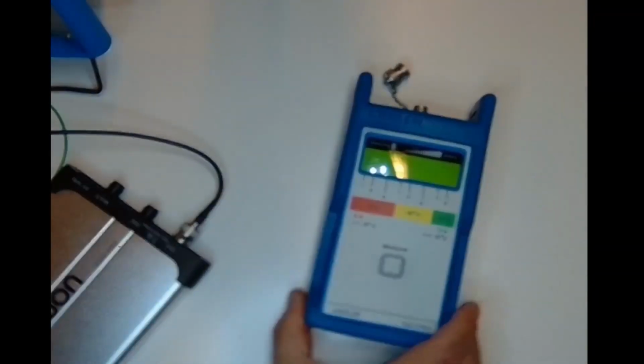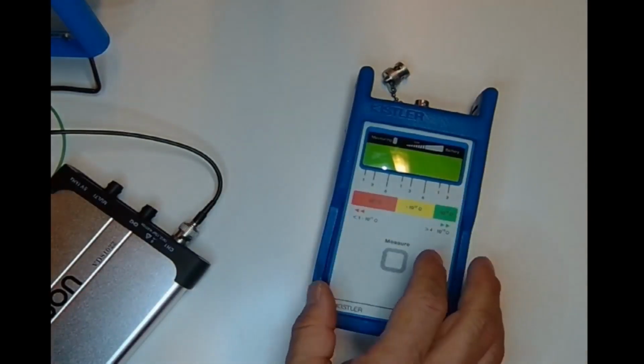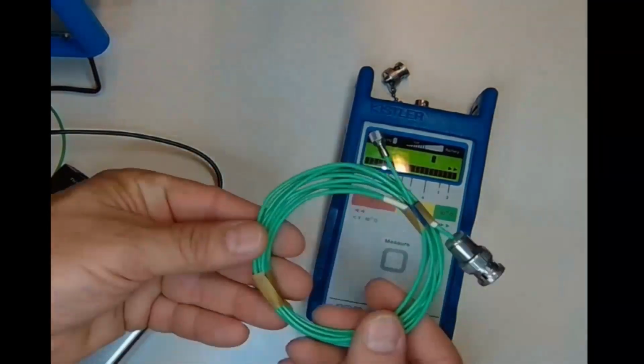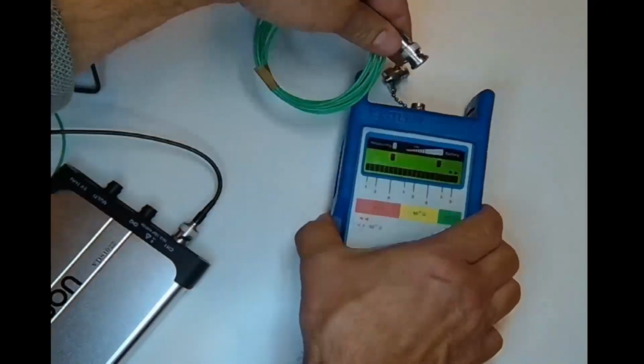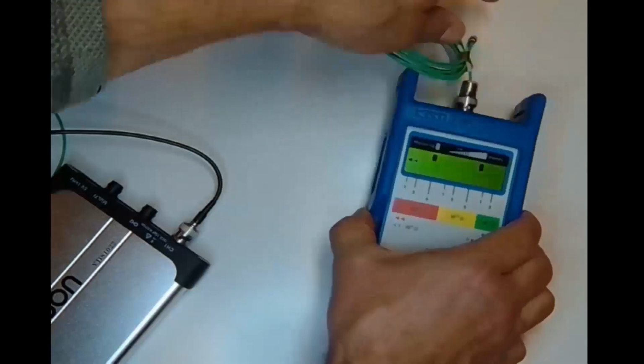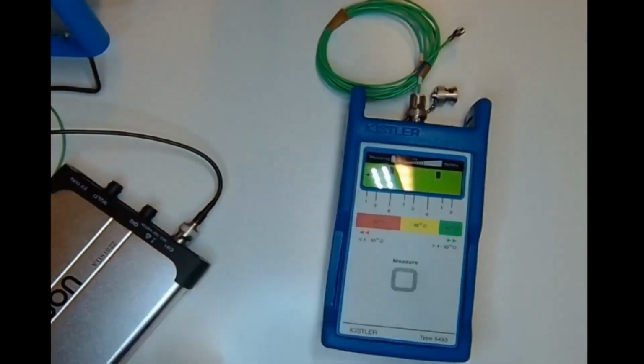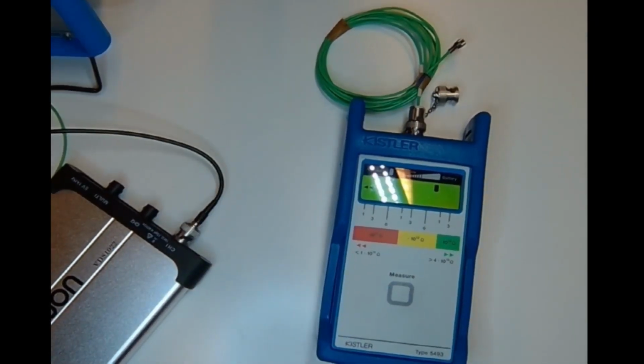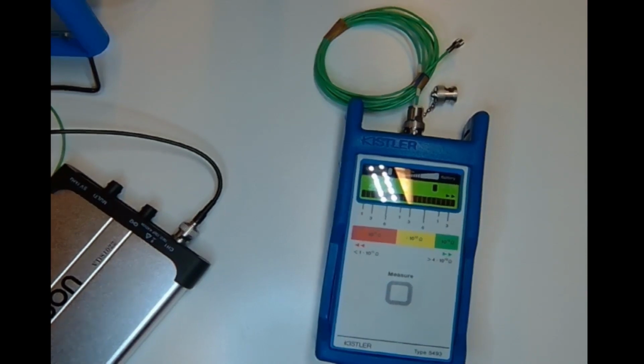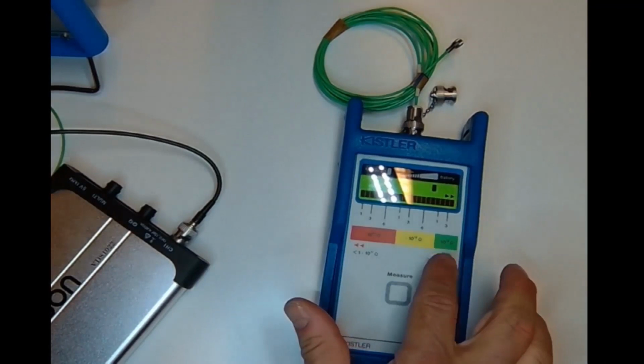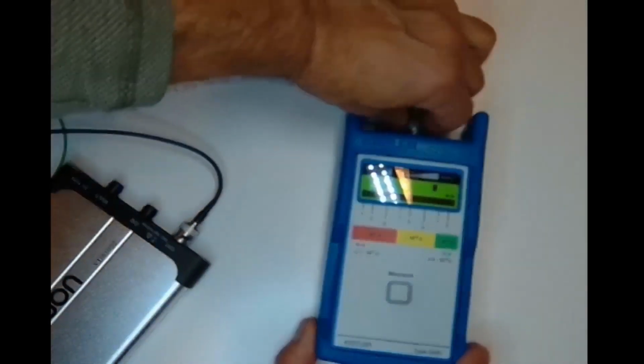We have a special tool, which is this battery handheld. You can start the measurement. Here is the cable, so we can just connect the cable. You see that the resistance dropped down, and we have to wait until the result is measured. The red means poor, the yellow means so-so, and the green area means good quality. So this sensor, as you can see here, has even higher resistance than 10 to the power 13. So this cable is in very good condition.